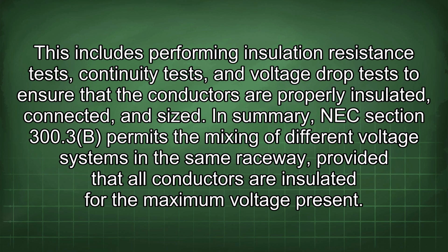This includes performing insulation resistance tests, continuity tests, and voltage drop tests to ensure that the conductors are properly insulated, connected, and sized. In summary, NEC Section 300.3b permits the mixing of different voltage systems in the same raceway, provided that all conductors are insulated for the maximum voltage present.